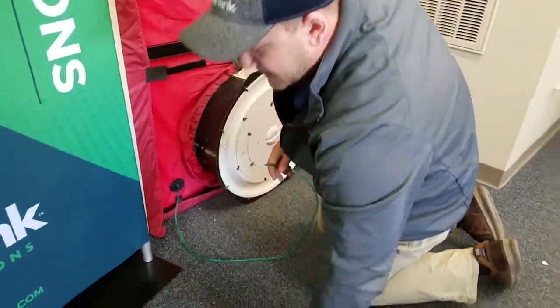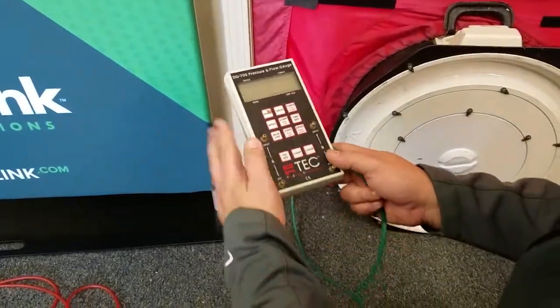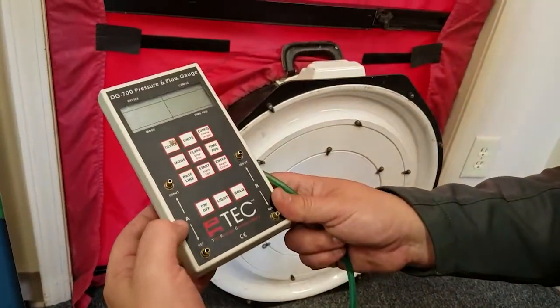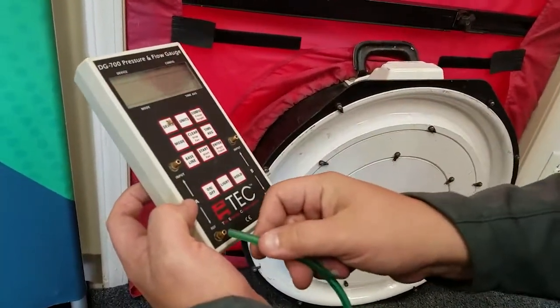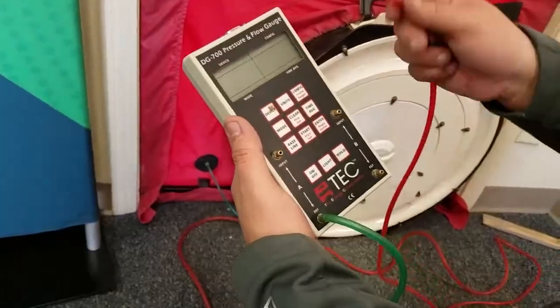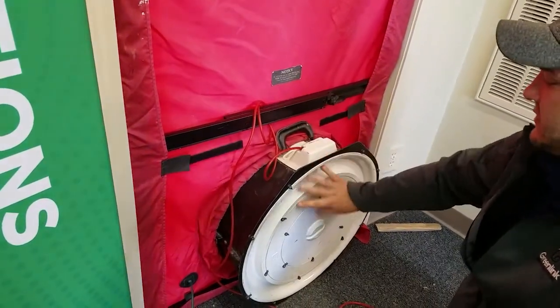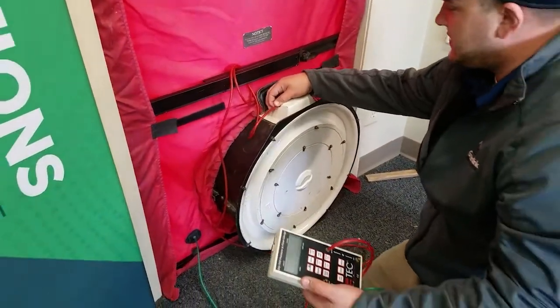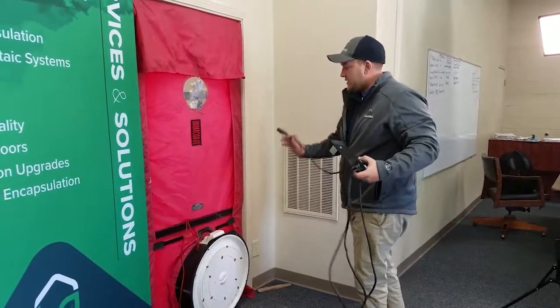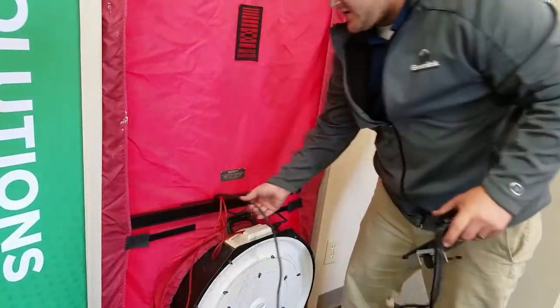Now we'll go ahead and hook up our hoses. We've got our green hose which goes to the A channel — the left side of the device — and then we're going to take our red hose and this is going to go to the input side of the B channel. You don't want hoses dangling in front of the fan in case it sucks something in there and chops it up. Last piece: we've got our power cord for our fan — plug that into the receiver on the side of the fan.